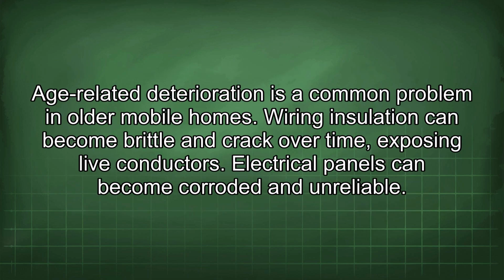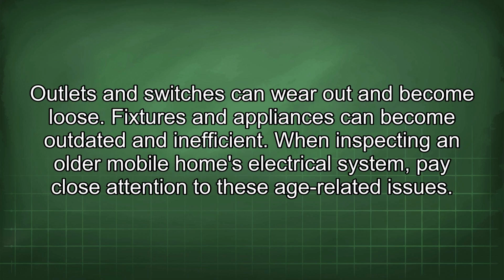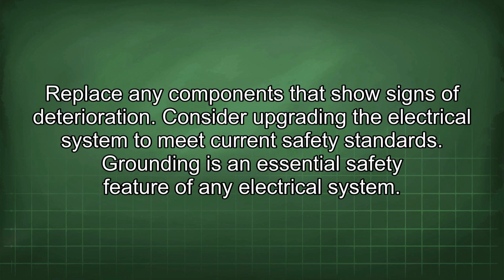Age-related deterioration is a common problem in older mobile homes. Wiring insulation can become brittle and crack over time, exposing live conductors. Electrical panels can become corroded and unreliable. Outlets and switches can wear out and become loose. Fixtures and appliances can become outdated and inefficient. When inspecting an older mobile home's electrical system, pay close attention to these age-related issues. Replace any components that show signs of deterioration. Consider upgrading the electrical system to meet current safety standards.